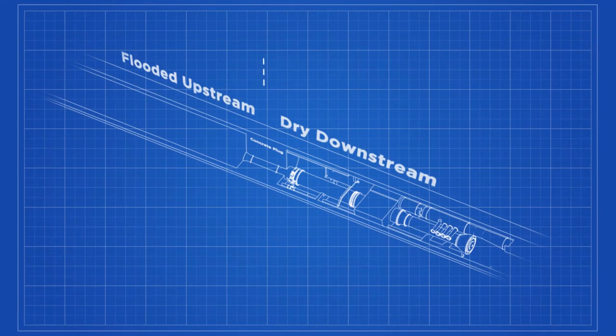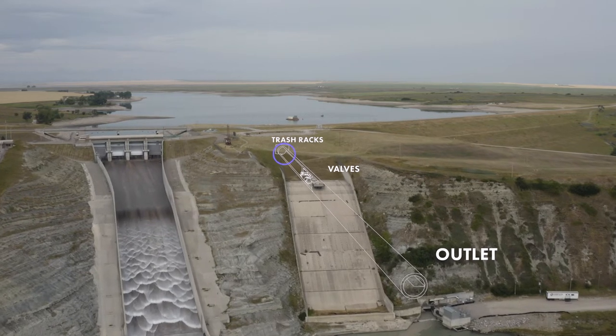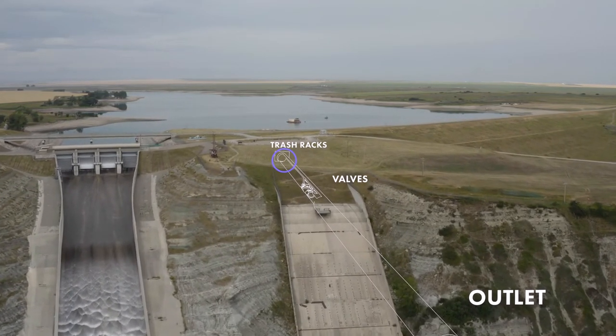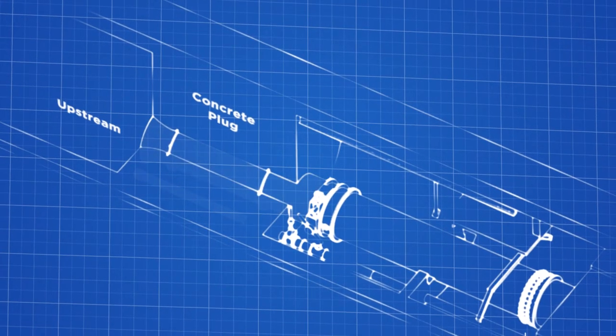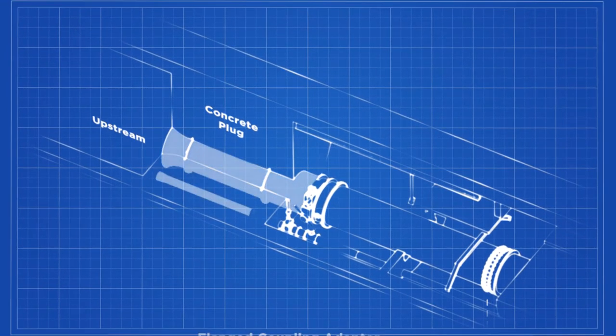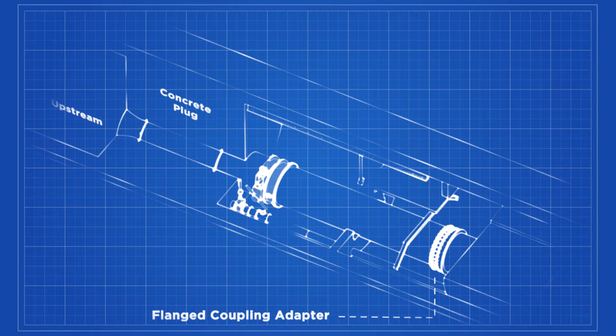Approximately 700 feet downstream of the trash racks, a concrete plug separates the submerged upstream end of the low-level outlet tunnel from the downstream. The concrete plug is 20 feet long and prevents the reservoir draining through the tunnel. Two conduits pass through the concrete plug. Immediately downstream of the concrete plug, there is a guard valve on each of these conduits. These valves are used to stop the flow through the conduits.